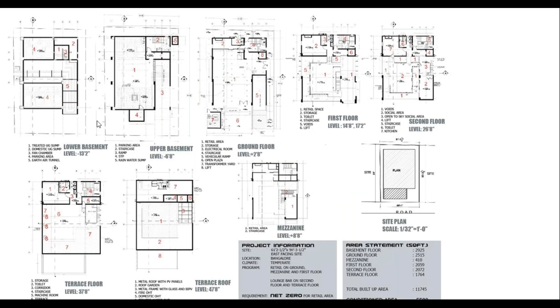To give a bit more detail on how we integrated the earth air tunnel, these were the four inlets we had, routed between the car park areas and continuing along the ramp. Because the space was limited, it was quite challenging to route the earth air tunnel. In a larger building we would not have had these issues, because if done incorrectly it would have been very difficult to service or repair, since it's at minus 22 feet 6 inches, very much underground in such a small space.